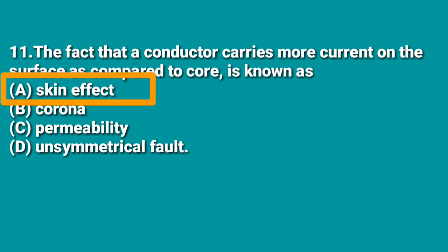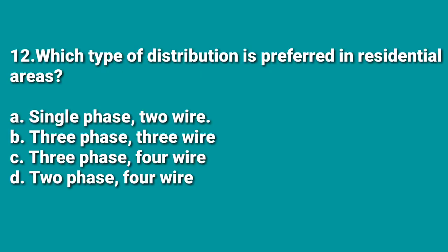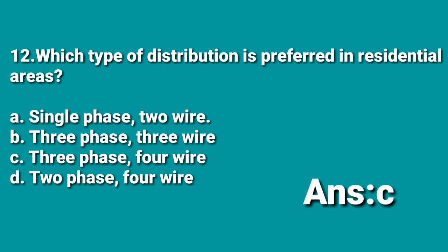The next question: which type of distribution is preferred in residential areas — A: single-phase 2-wire, B: 3-phase 3-wire, C: 3-phase 4-wire, D: 2-phase 4-wire? Normally in residential distribution systems, the 3-phase 4-wire system is preferable because the neutral wire must go to every house, and it can also withstand unbalanced loads. Hence the answer is C.